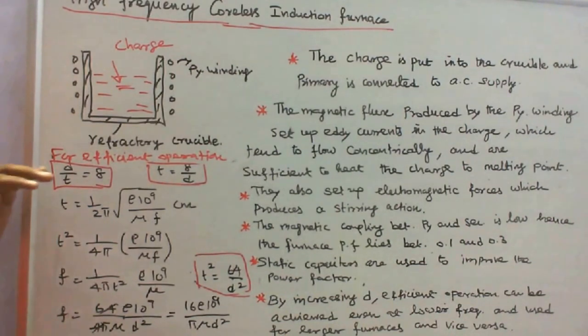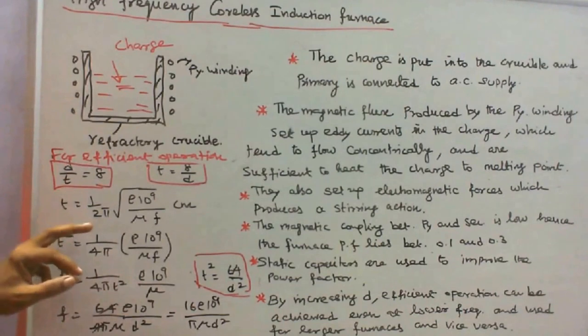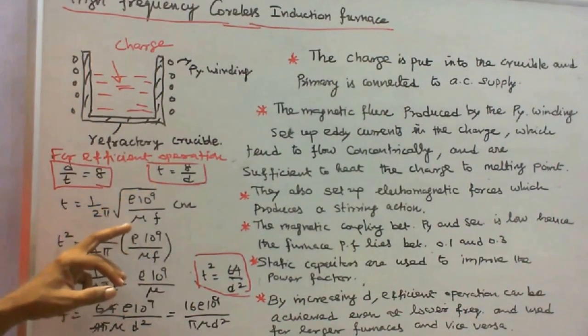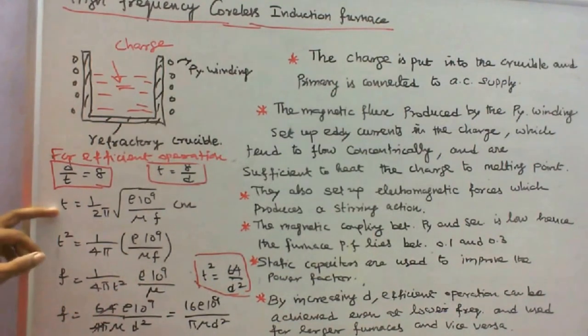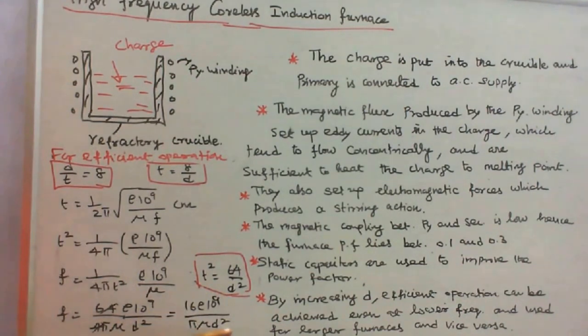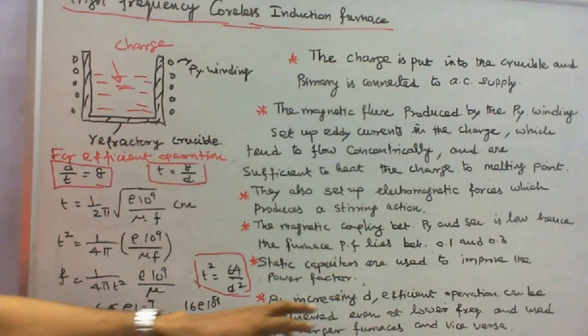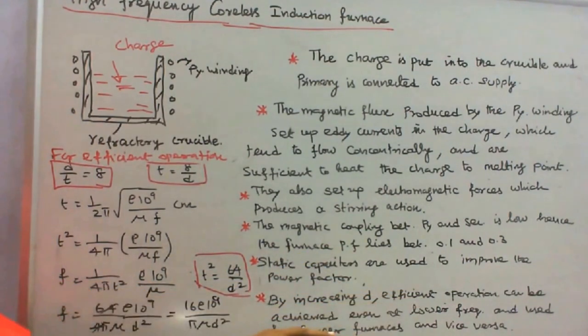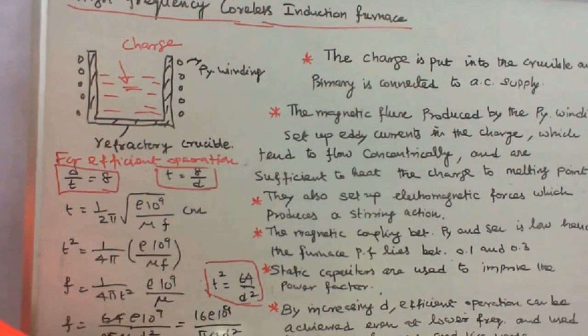Static capacitors are used to improve the power factor. For efficient operation, D/T = 8, so T = D/8. Substituting into the penetration formula gives: F = (16 × ρ × 10^9) / (π × μ × D²). By increasing D, that is the diameter of the charge, efficient operation can be achieved, and this formula is used for larger furnaces. The inverse holds for smaller furnaces.